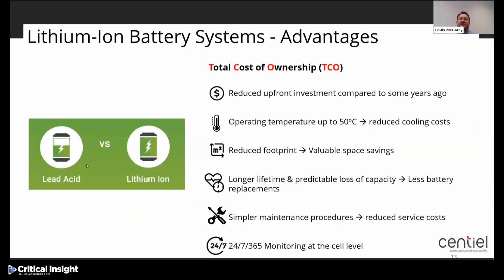Now, to be able to perform this type of operation, the energy storage product that's attached to the UPS must be considered. Whilst the most common energy store for a UPS system is a VRLA battery block, which is widely available, tried and tested, and is relatively green, it is mainly used for standby applications due to its ability to only perform maybe 100 or 200 full cycles in its lifetime. This means that selecting a product that has a long life and can perform thousands of cycles is key to being able to perform this task on a daily basis, if not a weekly basis. And so our attention turns to products such as lithium-ion batteries.